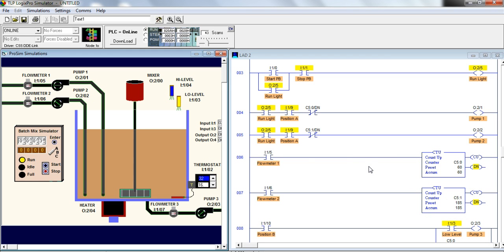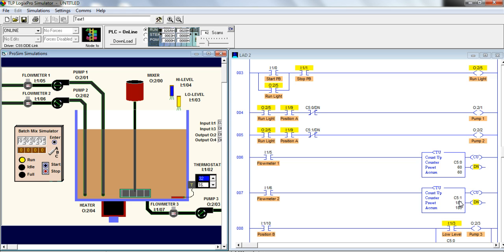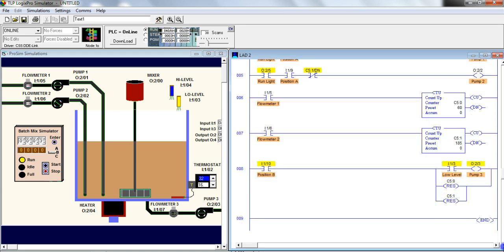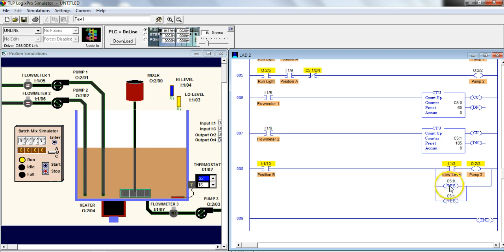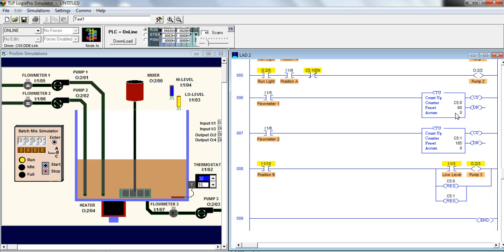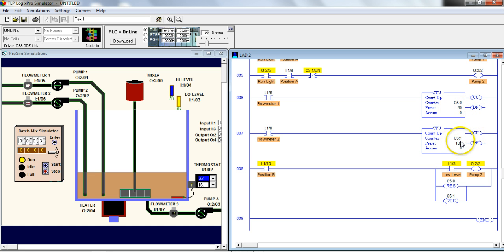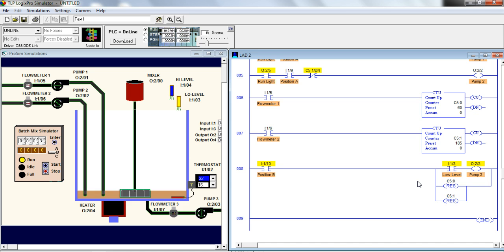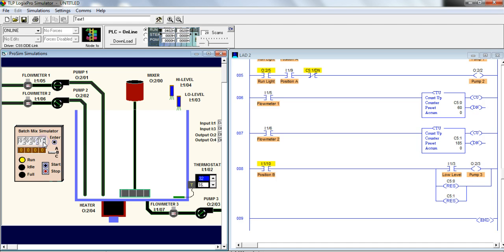So this was recipe 3. So recipe 3 puts 60 counts of one product and 185 counts of the other product. I'm going to go to position B and empty this. I have that right down here in my code. Position B empties it. And it also will reset my counters. So it's very important to remember that any counter will need a reset. And you'll see my accumulation value went to zero as soon as I reset them.